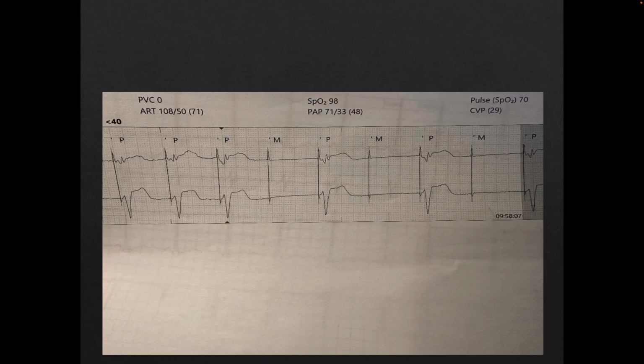And then look at this spike, and this one here, and this one here. What is that called? Intermittent loss of capture. Exactly. Good. So it's not oversensing or undersensing, right? So it gives an output. If it was undersensed, you would see a ventricular beat, right? And undersensed and still gave an output afterwards. So this is failure to capture.